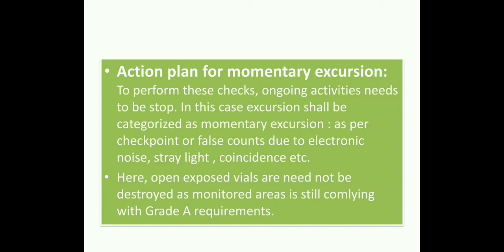Not taking further action on the filling process can be justified with the rationale that the clean room area requirements for Grade A are managed and complied with, so we are not taking any action on filled vials or open exposed vials. To perform the mentioned checks, ongoing activities can be stopped. As per the checklist, the excursion can be categorized as a momentary excursion due to electronic noise, stray light, or coincidence, and open exposed vials or filled units need not be disturbed or destroyed.